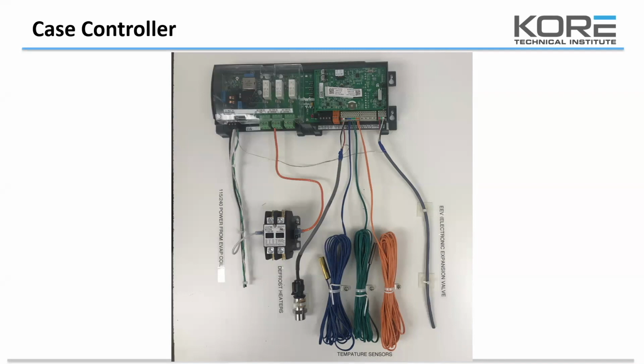We do have a suction or a 200-pound transducer that is shown here. That may or may not be at the coil. We can, through the program, use the suction transducer that's already mounted up at the condenser for this purpose. You've got a blue temperature control on the head of the sensor there. It actually has a concave or a pipe fitting on it that makes it easy to attach it to the refrigeration pipe, and this is going to be located at the outlet of the evaporator coil so that we can see the temperature of the coil itself.